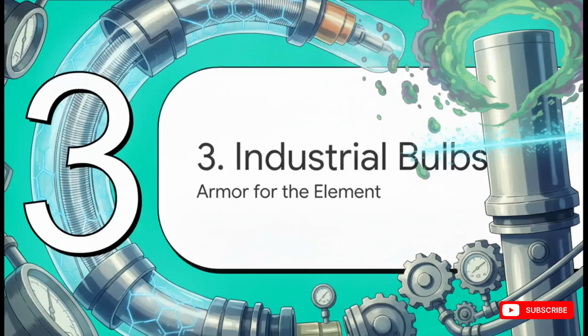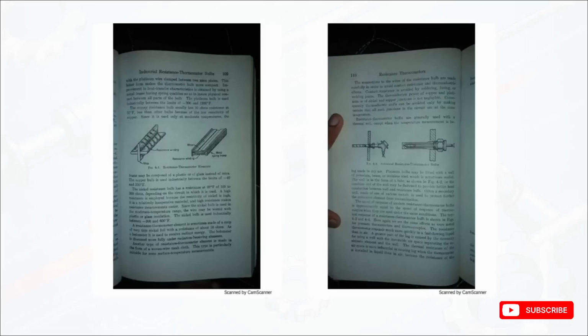Section 3, industrial bulbs, armor for the element. When you compare that naked internal winding to the heavy-duty industrial bulbs required on a plant floor, the difference is huge. To stop oxidation and contamination from, say, harsh industrial gases or liquids, that fragile mica-clamped platinum element gets totally sealed inside a well made of porcelain, brass, or even stainless steel.